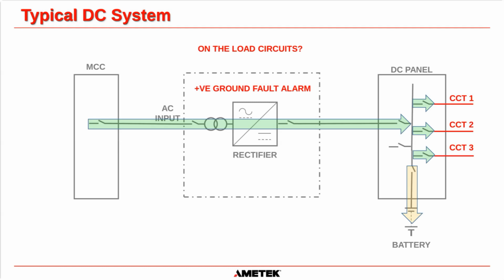And once again, we're working in the ideal world, and we can switch off these breakers one at a time. And that is what you have to do. So we switch off circuit one. If the fault goes away, then the fault is on circuit one. Okay. If we open circuit one and the fault remains, that means it's on either circuit two or circuit three. So we move on. We move to circuit two. We open that breaker. If the fault stays, that means we know it's going to be on circuit three. If the fault goes away, then we know the fault is on circuit two.